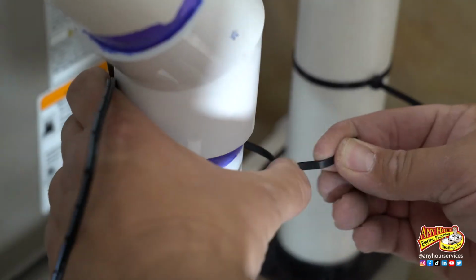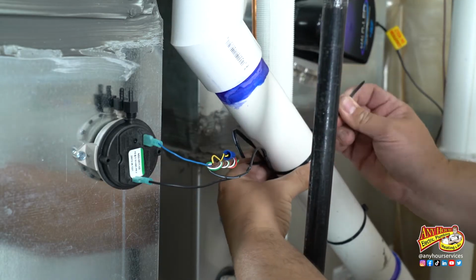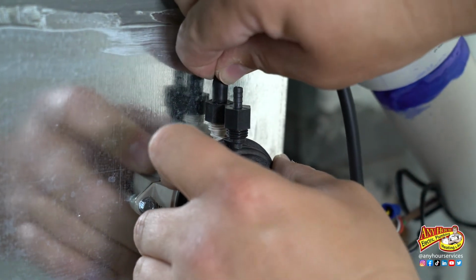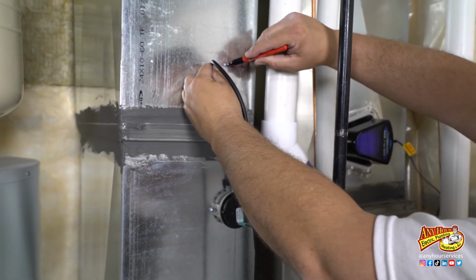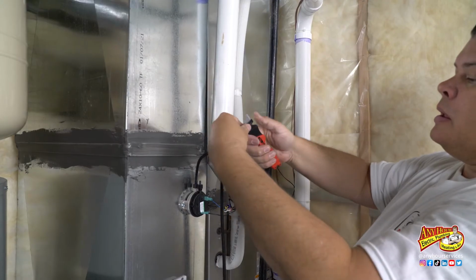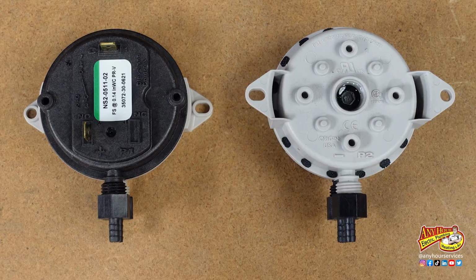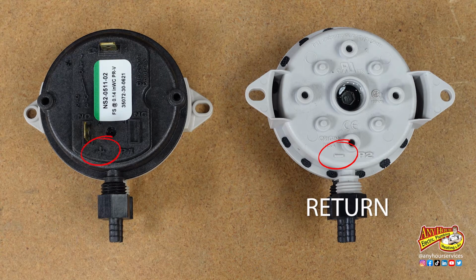Now you can go back and secure any loose wires and trim up any zip ties you may have left. The last thing we need to do is run the vacuum hoses from the air switch to the return and supply ductwork. The negative side of the air switch is going to go to the return, and the positive side of the air switch is going to go to the supply.